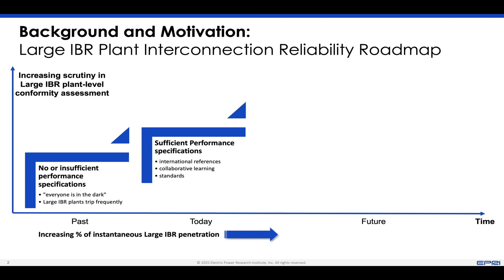Some people could say conformity assessment could simply be done by checking a box whether an inverter or other equipment has been certified, with a checklist for the plant. That takes us farther than before, at least verifying that the inverters could ride through voltage dips or provide a certain reactive power to the IBR plant. But really, the gold standard is to look at the whole plant in detail using validated equipment models.